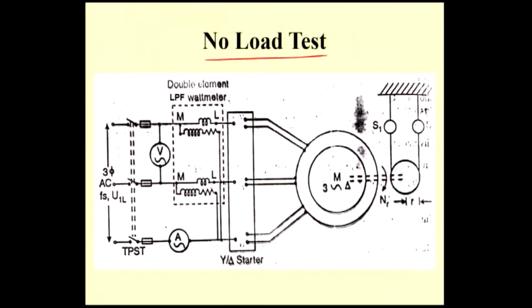We can conduct the no-load test using the LPF meter. While conducting the no-load test, the Nr value is approximately equal to Ns. That means you have to allow the rotor to rotate freely. You are giving the rated voltage while conducting the no-load test.